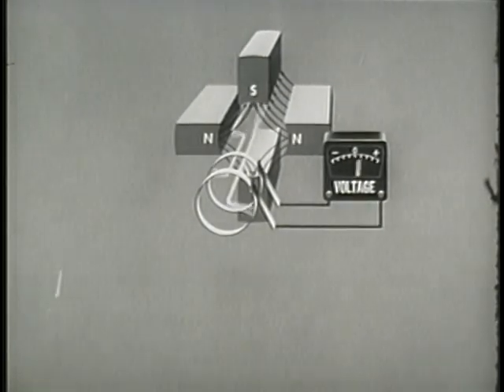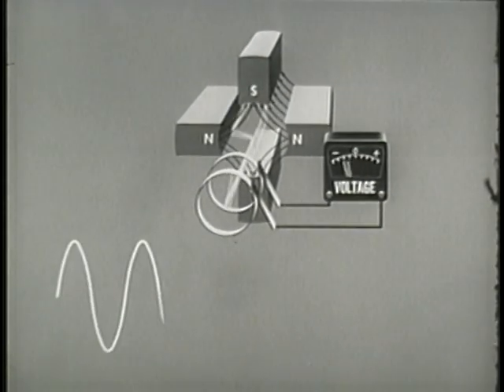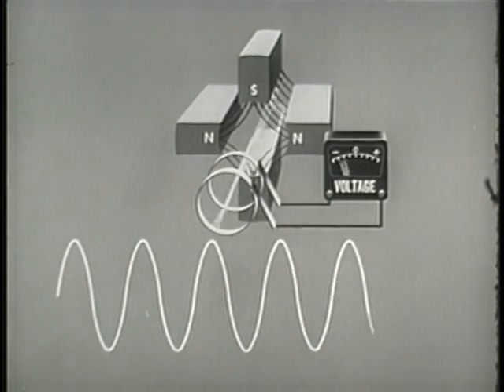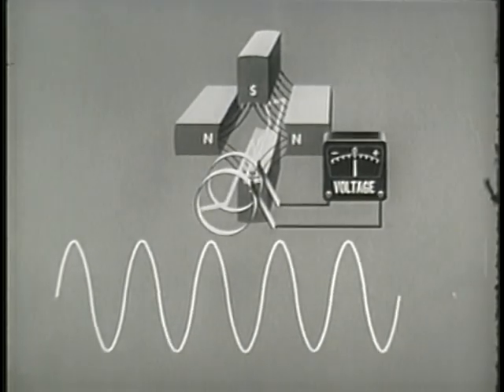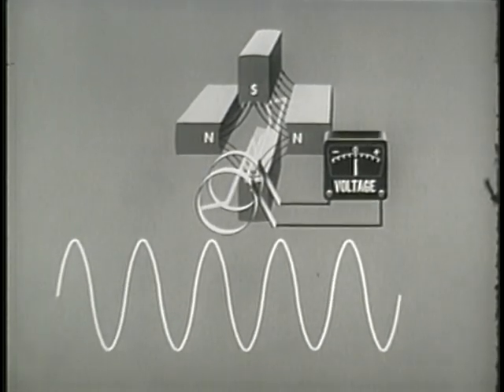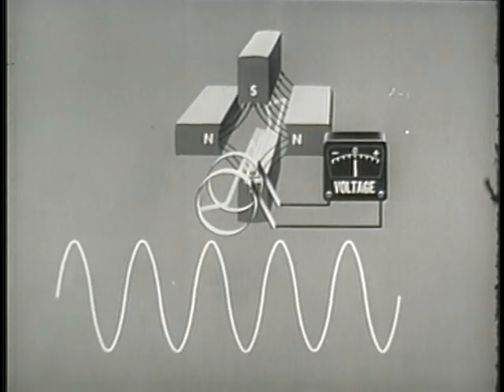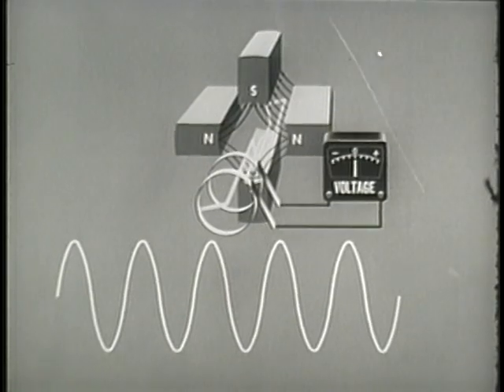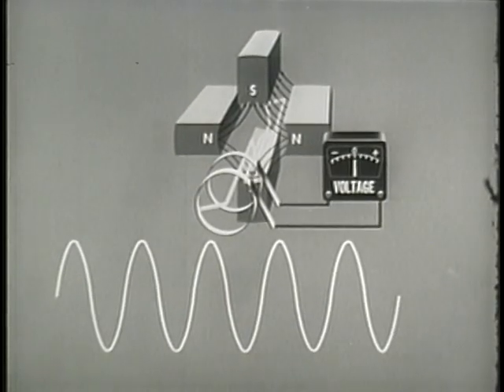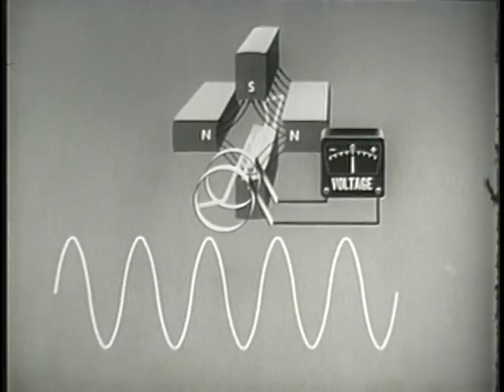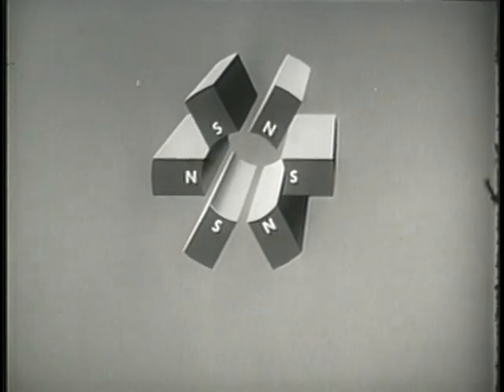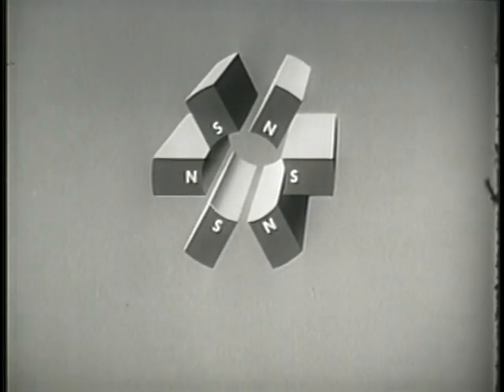Frequency can be changed in the AC generator by the introduction of additional magnetic fields. The relationship between mechanical and electrical degrees depends on the number of poles in the generator field. In a four-pole field, 360 mechanical degrees equals 720 electrical degrees, a ratio of one to two. In a six-pole field, the ratio is one to three, and so forth.